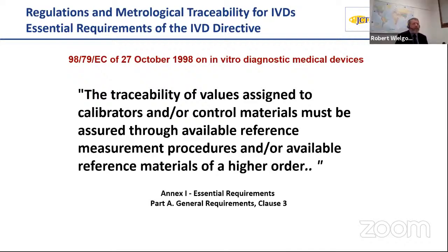So the essential requirement in that regulation was this: the traceability of values assigned to calibrators and control materials must be assured through available reference measurement procedures and/or available reference materials of a higher order. And so the first problem for the IVD industry was to understand which of these materials and methods were available.